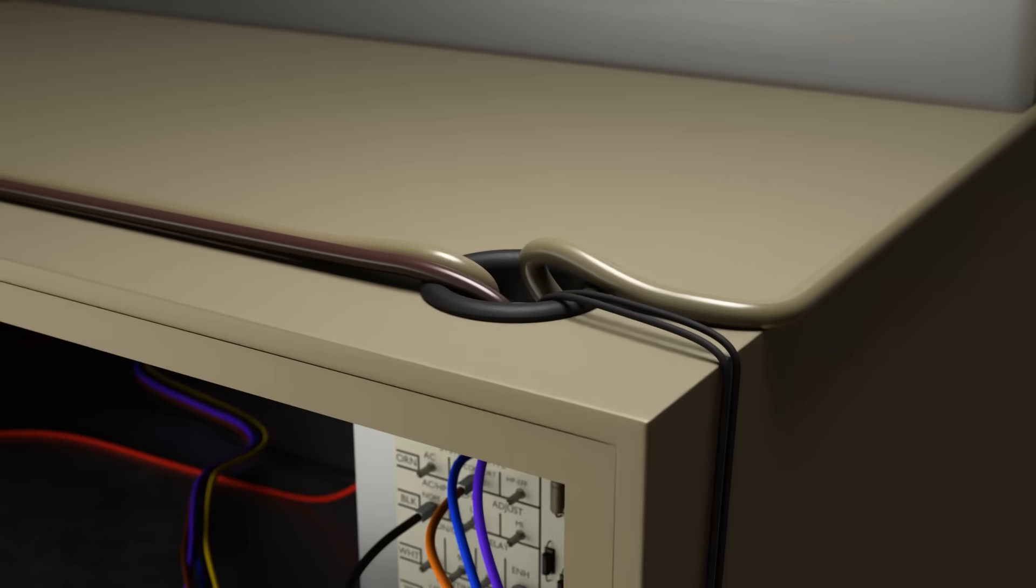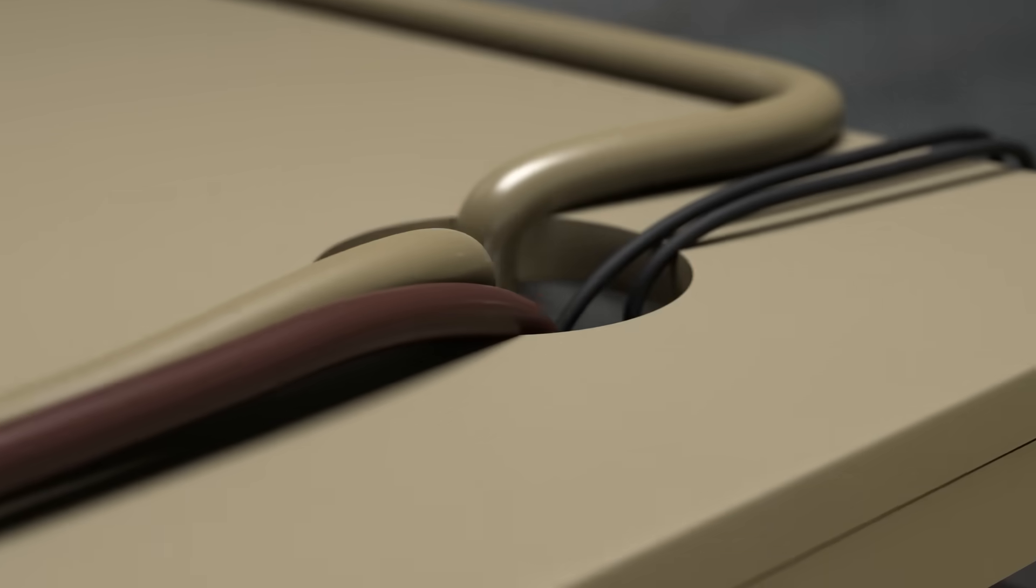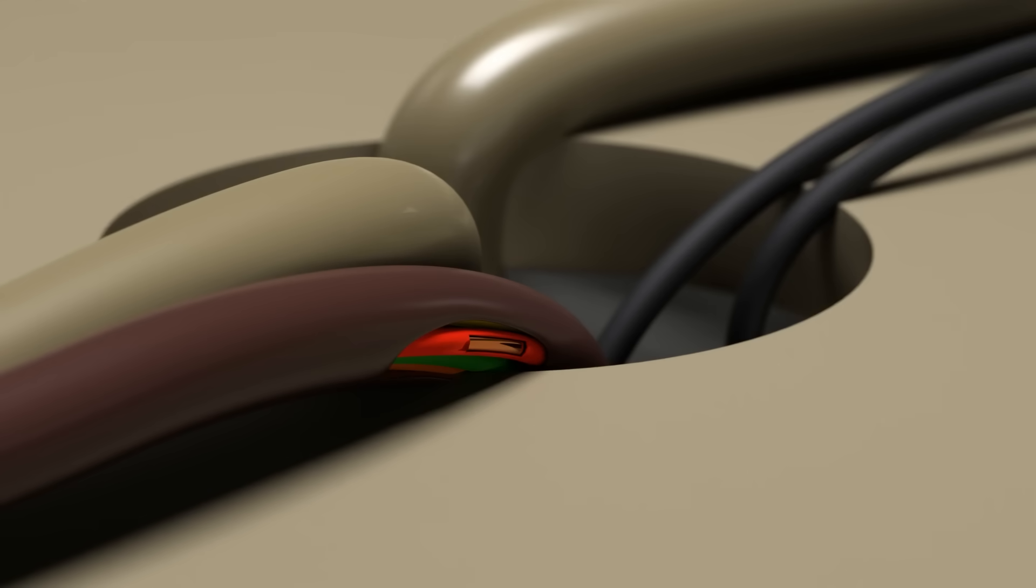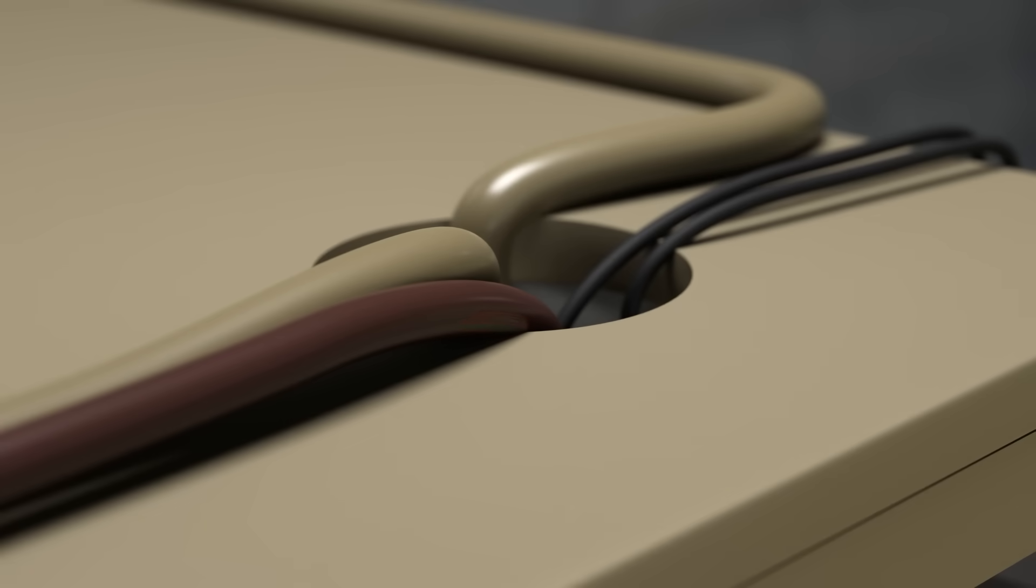Make sure to use appropriate grommets or connectors when routing wires or cables through the cabinet. This is a common source of chafing and abrasions, which can lead to short circuits if done improperly.